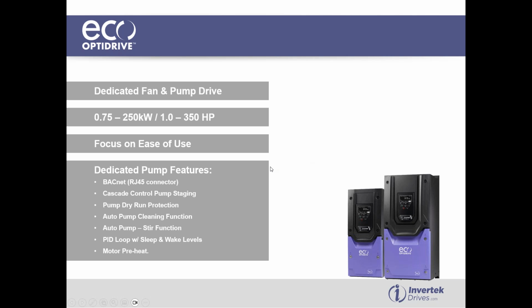We've got, as I mentioned, dedicated pump control features in there, as well as BACnet and Modbus RTU on board as standard. We can do cascade pump control, dry run protection, pump cleaning, and also pump stir functionality as well. So because we have the PID loop in the drive, where we can feed a transducer directly back to the drive, we've also got a sleep function in there.